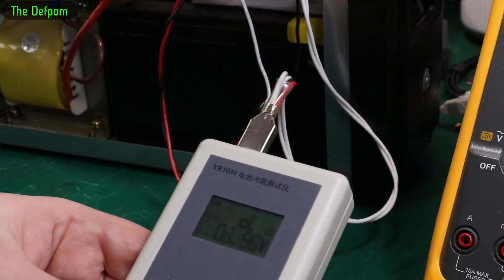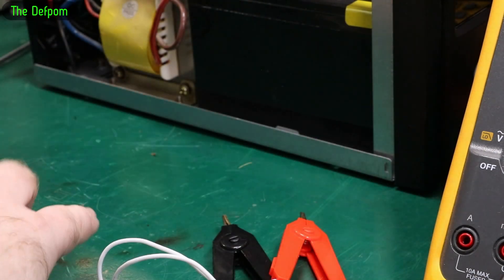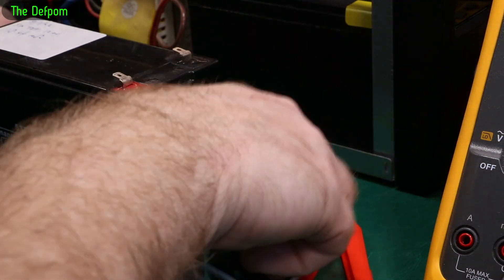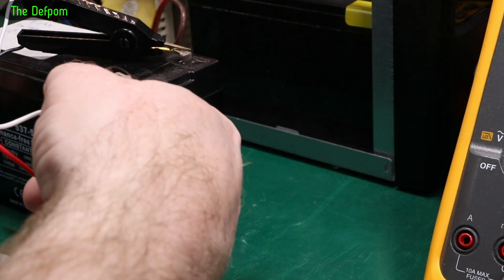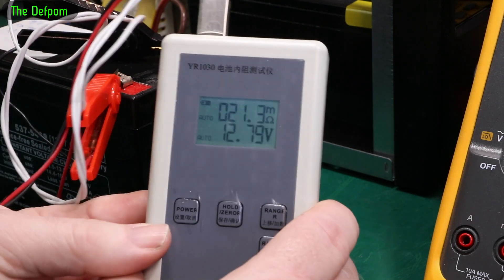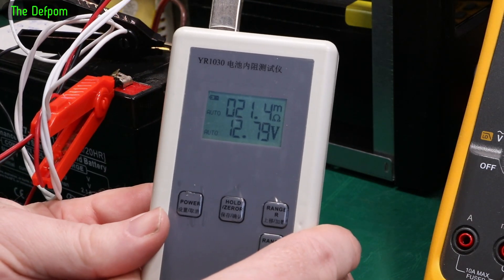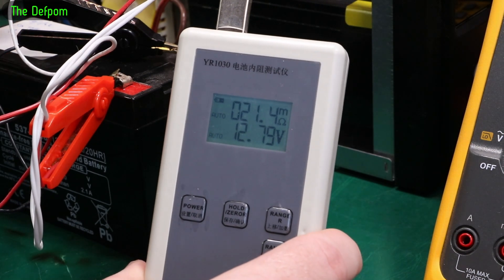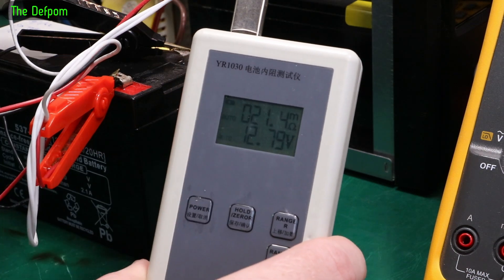Let's hook this up to the new battery — the internal resistance is probably higher than I originally tested since it's been sitting around, but it's probably going to be a lot better than 79 milliohms. It's probably going to be a bit more than 18 milliohms since it's not fully charged — internal resistance changes with charge level. 21 milliohms. When it's fully charged it should come down slightly, closer to the original 18 milliohms. It's still significantly better than the battery currently in this UPS, and the voltage is fine.